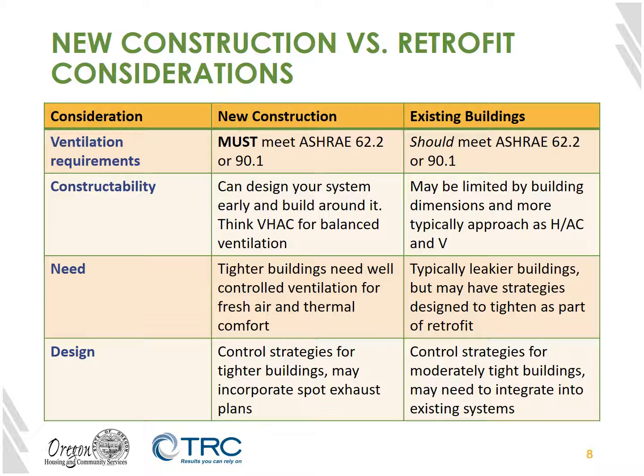These ASHRAE standards are constantly evolving, and they actually prefer balanced ventilation. In fact, future iterations of code and future iterations of the ASHRAE standards are considering adding penalties to buildings that do not build with balanced ventilation. So if you want to use the least amount of outdoor air to be pushed into a building, starting with balanced ventilation will be important. With existing buildings, there's not the same level of requirement, but it still should be considered, particularly because activities such as replacing siding, insulating buildings, changing out windows and doors are all likely to make an existing building tighter. And when we do that, the need for ventilation is going to really apply.